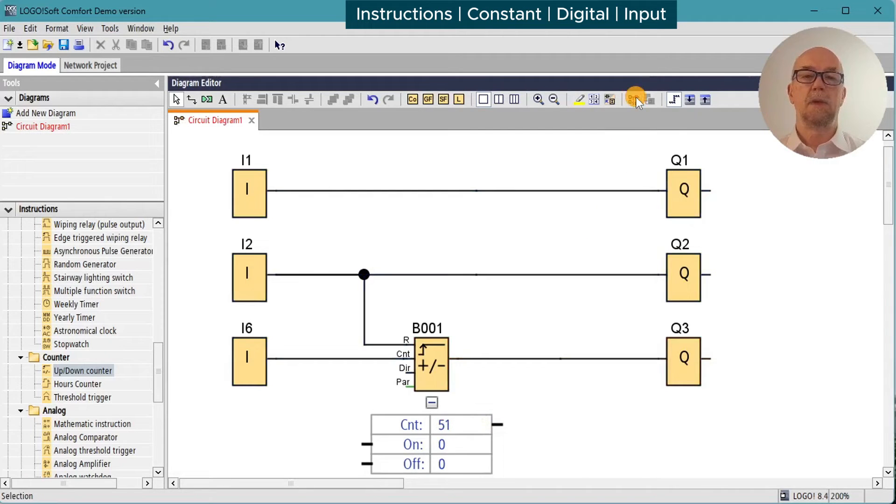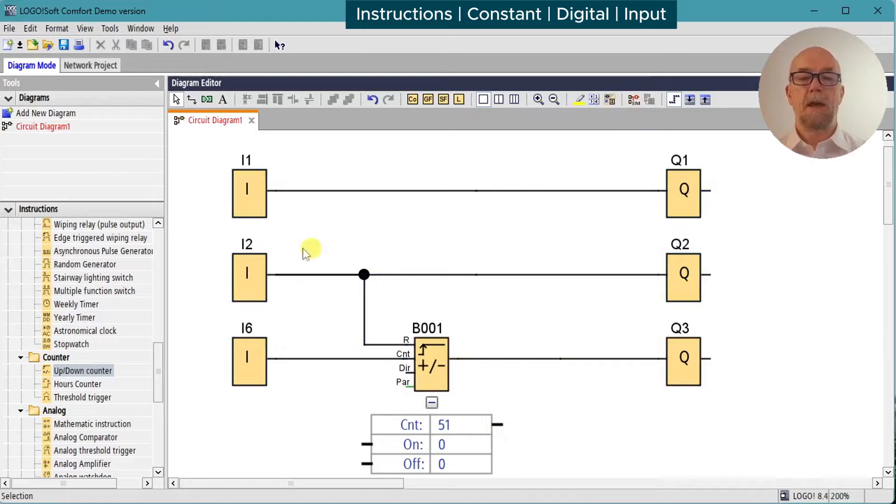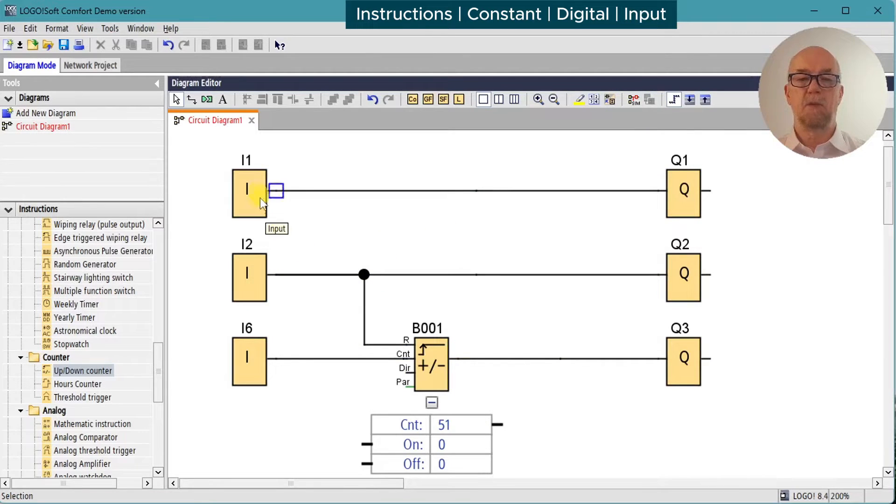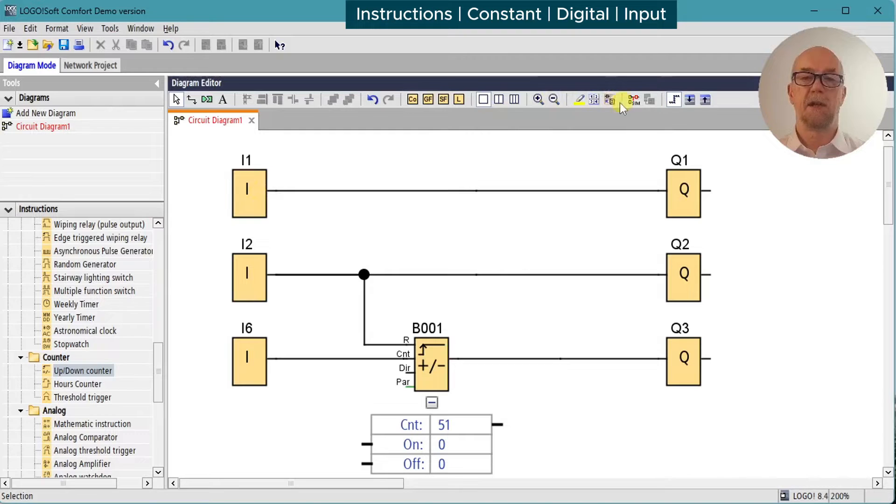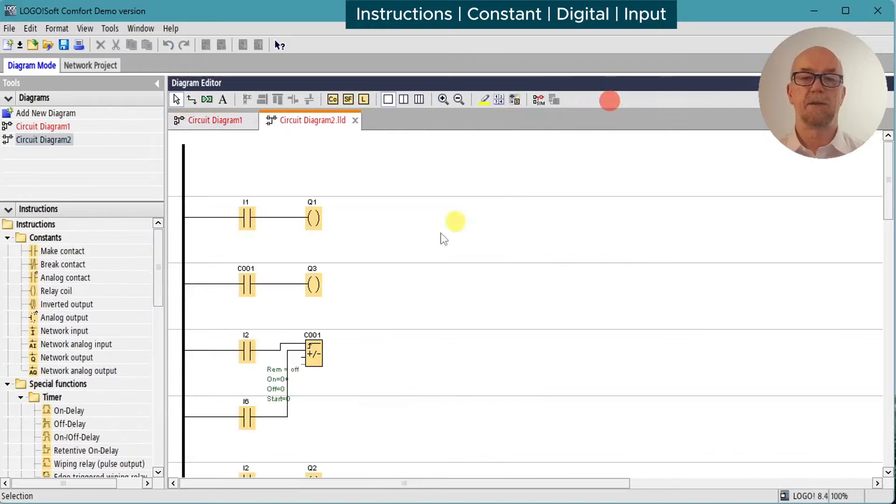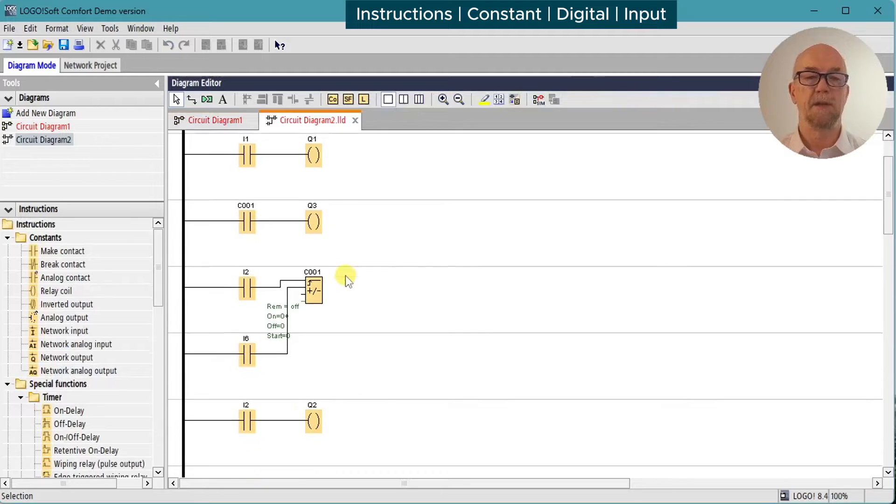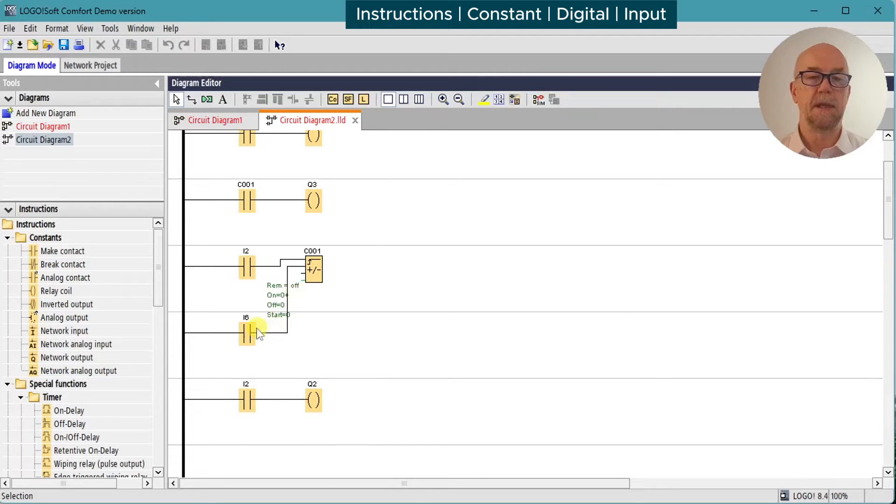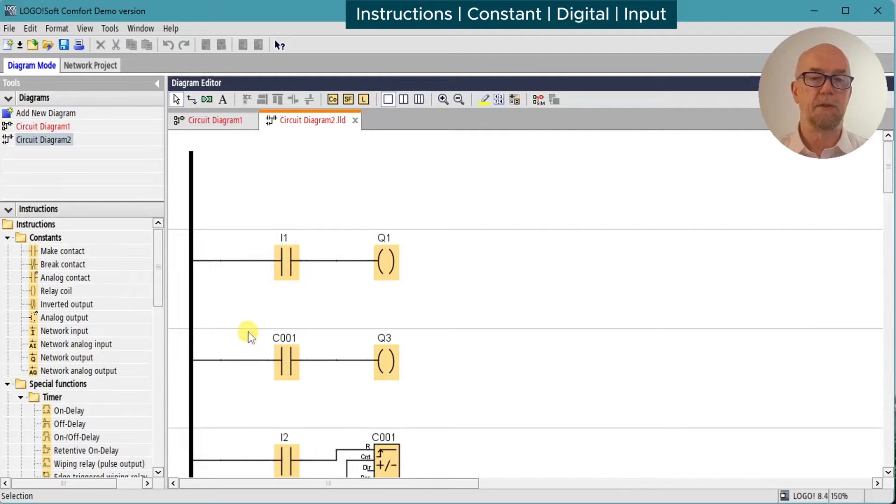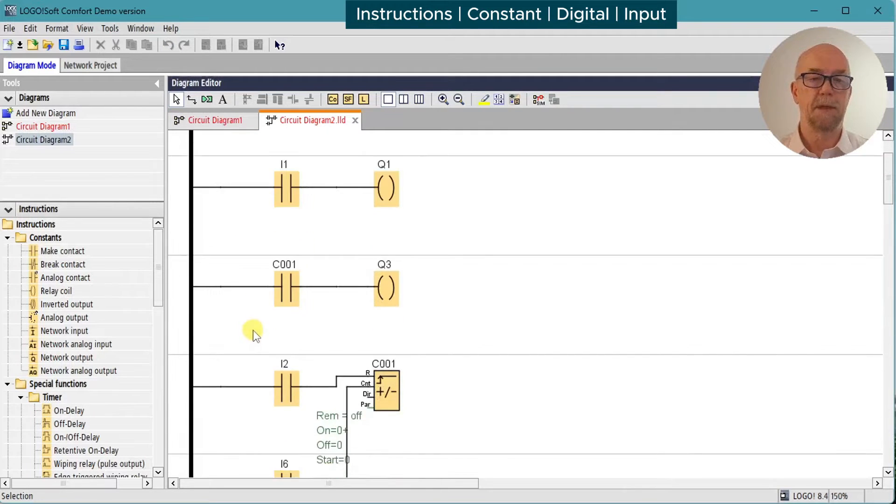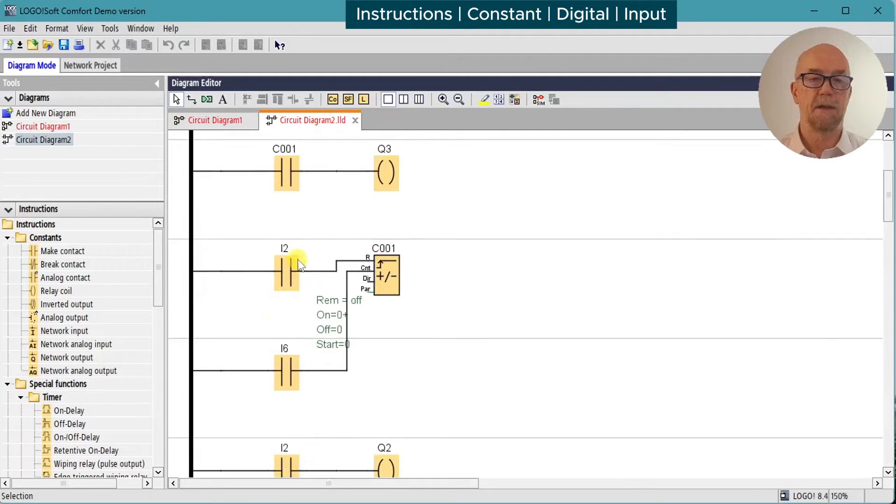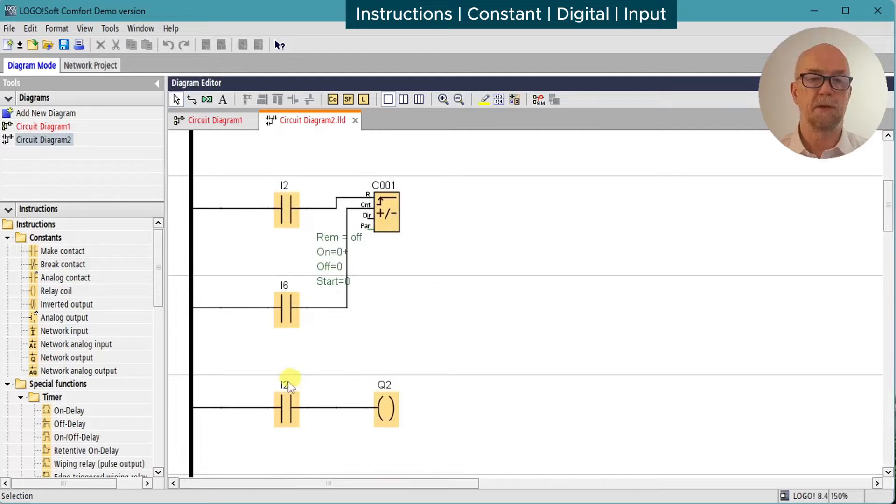We can do all that in ladder mode as well. I pointed out that each input can only appear once. That's not a restriction on the ladder, so it's one of the reasons why the ladder can be a little bit easier to read on a larger diagram. So here we see input 2 appears on this rung, but it also appears on this rung.